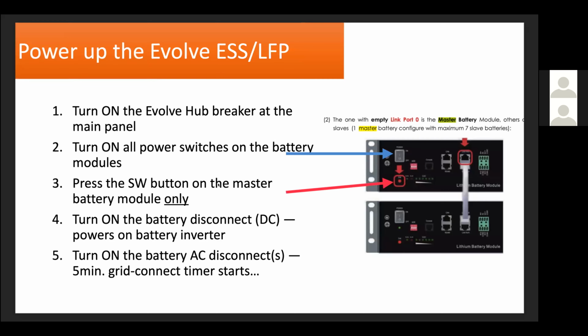Once you've got everything installed, wired up, and CTs are landed properly, then it's just going to be a matter of powering everything up. Quick review of the power up sequence is similar to a string inverter. You want to turn the DC on first, then the AC. The one exception being the Evolve hub breaker at the main panel will supply grid voltage to the EMS and to the normally closed ATS contactors, which would then serve the backup loads panel.